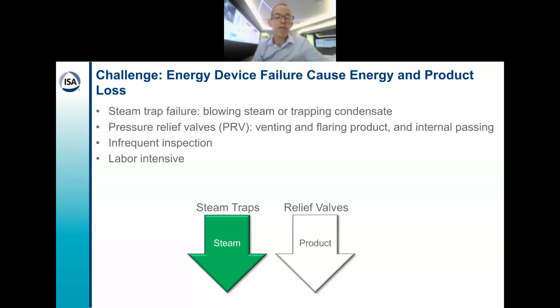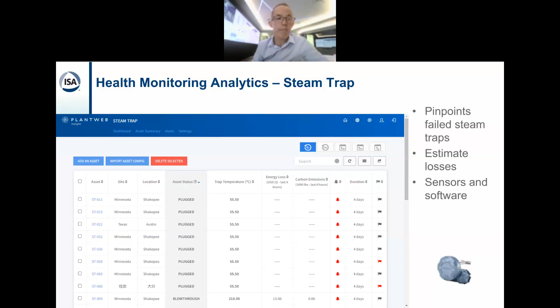So the recommendation is to automate steam trap monitoring with automatic data collection and analytic software to tell the health of these traps. Once failure is detected, you can replace them immediately. By getting data once a minute instead of once a year, you can minimize steam loss. This improves energy efficiency and sustainability. Again, these software apps are off the shelf, so no coding required. Again, wireless HART is the most practical way to deploy sensors.